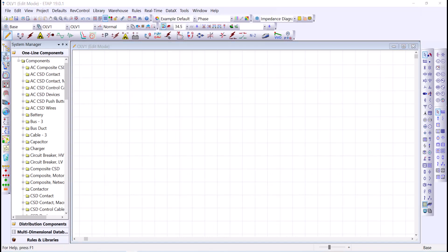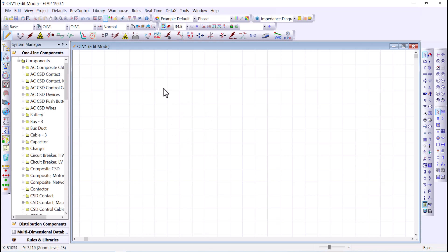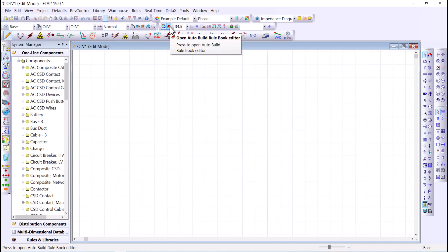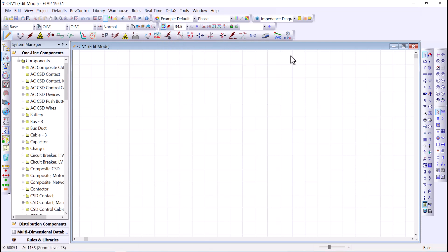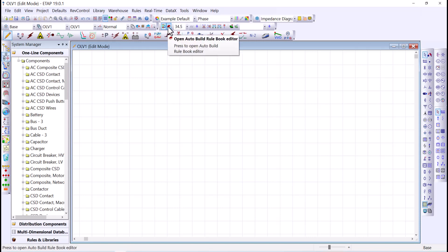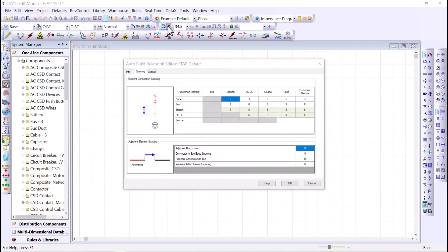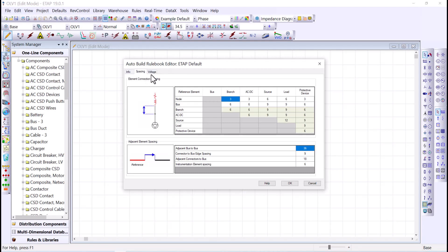Tip number nine is auto build. Auto build provides a quick and consistent way to build your one-line diagram, making it more appealing and easier to read by using a rule book that dictates spacing between elements and supports voltage propagation. You need to activate auto build first. Before building, understand the rule book, which has three tabs: information, spacing, and voltages. The spacing tab provides rules about spacing — for example, the distance between a node and a branch is about three units of length, and between a bus and a source is nine units.